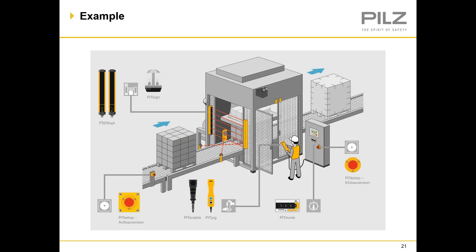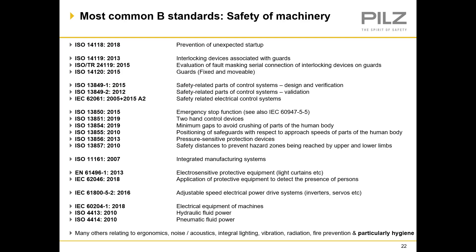The most common Type B standards for packaging machines include: EN 14118 — prevention of unexpected startups; EN 14119 — interlocking devices associated with guards; EN 13849 parts 1 and 2 — safety-related parts of control systems, design, validation and verification; EN 60947-5-1 — control devices; and EN 60204 — electrical equipment of machines.